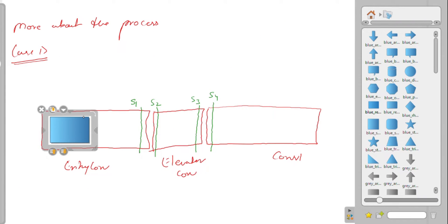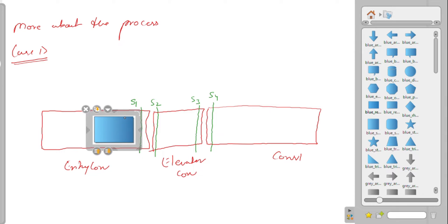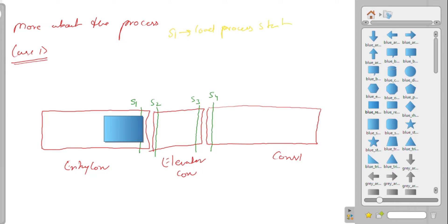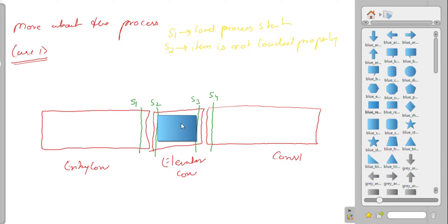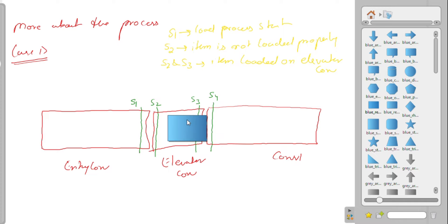When the entry conveyor is on, the item or box will start moving towards the elevator conveyor, so sensor S1 will detect the pallet, meaning we need to turn on the load actuator. At that time S2 will turn on just a moment after, indicating that the box is being loaded but not loaded yet. When S3 and S2 are both not detecting anything, it means the item is perfectly loaded on the elevator conveyor.